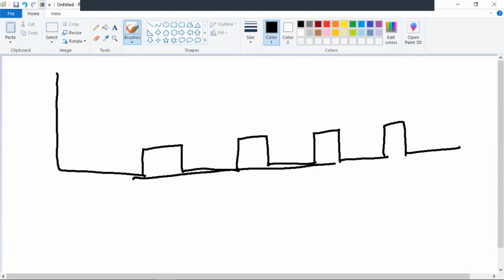Okay, here's my transformers. What we would do is we'd have the blown fuse here. That's our first indication we got bad cable. We would come to the first transformer and pull one elbow off. Close the fuse. If the fuse blew, then we knew it was in the first span. If the fuse held, we go to this next transformer, pull an elbow off, put this one back on. If it blew the fuse, you see where I'm headed? We knew it was in this span.